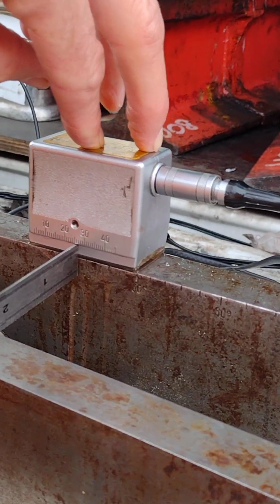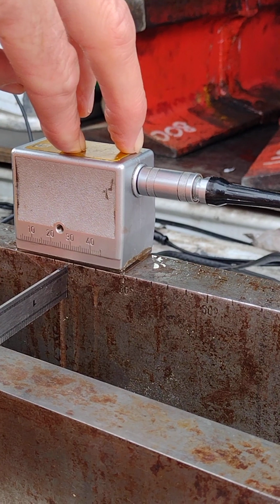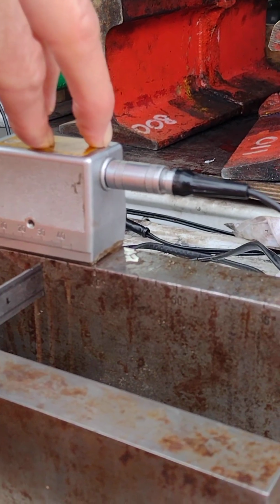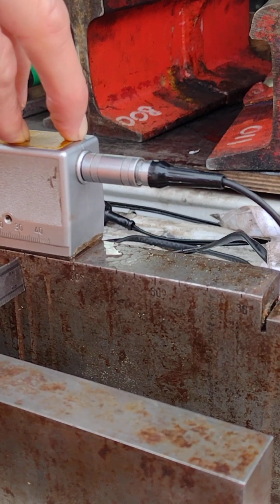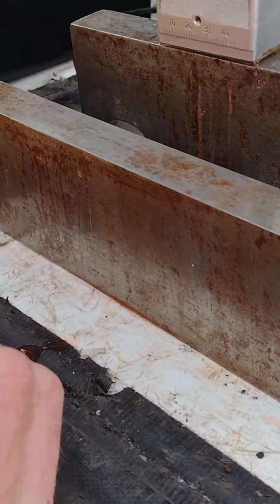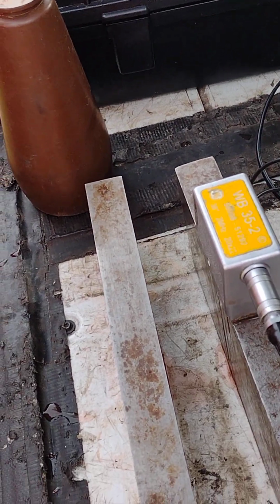block. Now our index point was 25, it lines up pretty much smack on what would potentially be the 38 degrees. So the probe is well within specification. We've got plus or minus 2 degrees allowed, and that is spot on. Alright, we've now got our probe all sorted out.